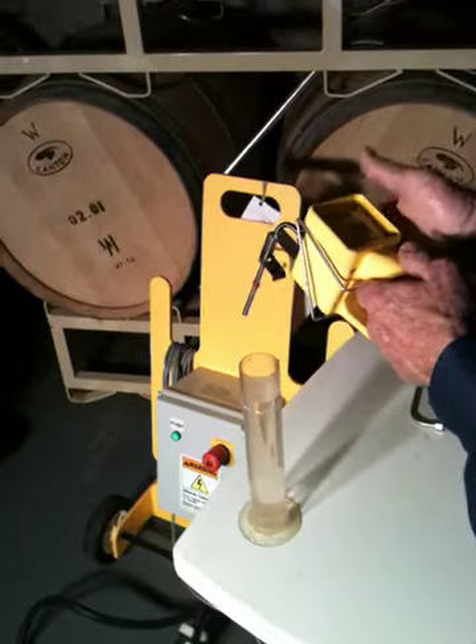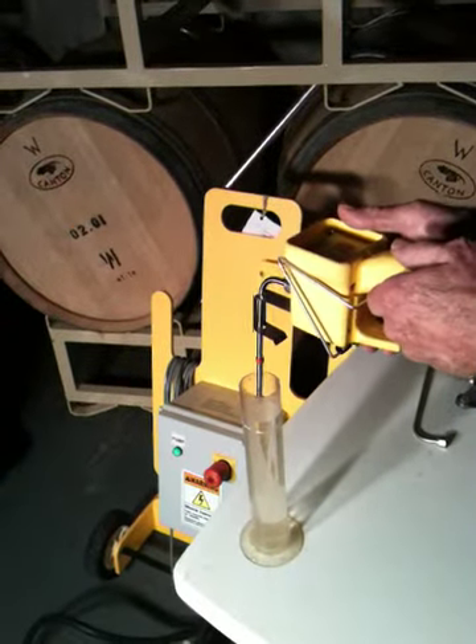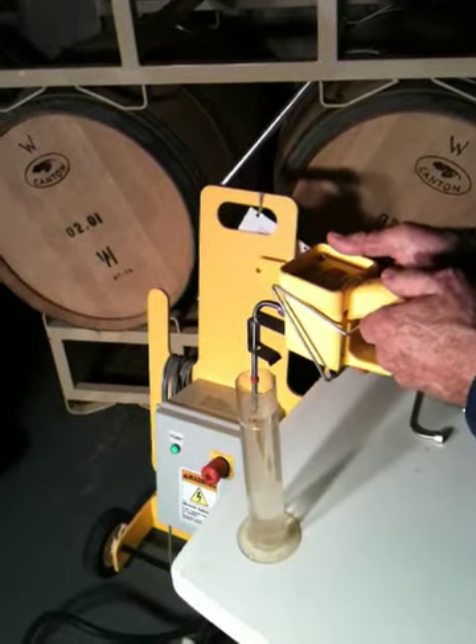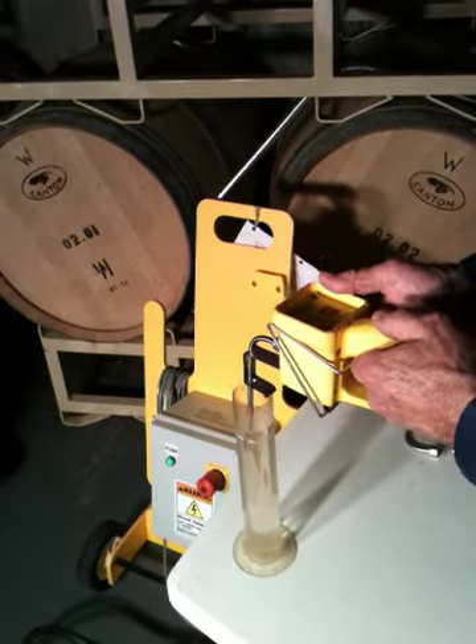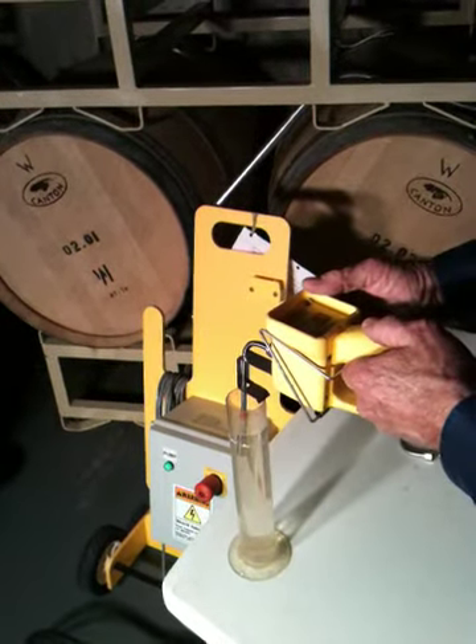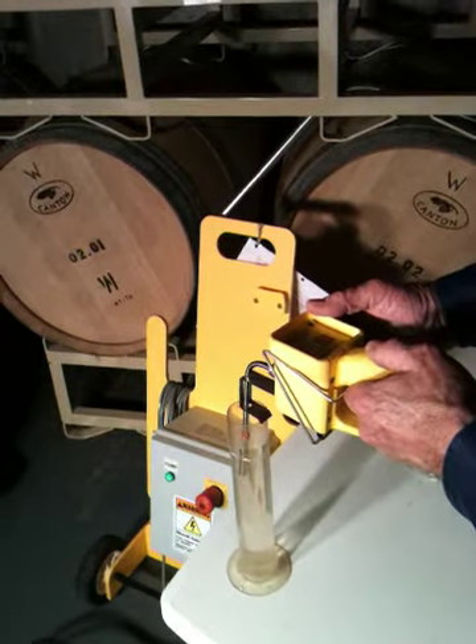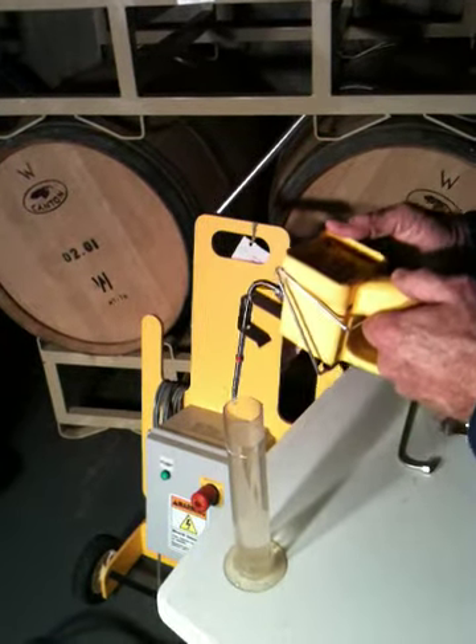So if you can see the green light, I want to hit start. And it should be running the pump. So if this is in a barrel, as the wine level reaches up and gets higher and higher, it approaches the red band, you watch the green light, it should go off when it reaches the band. And there it is. That's the calibration.